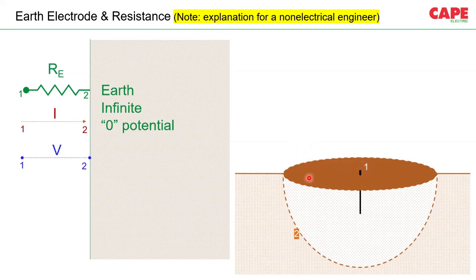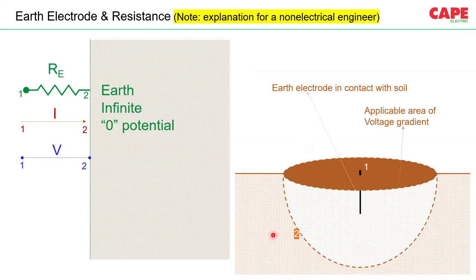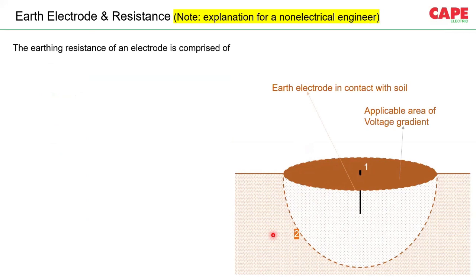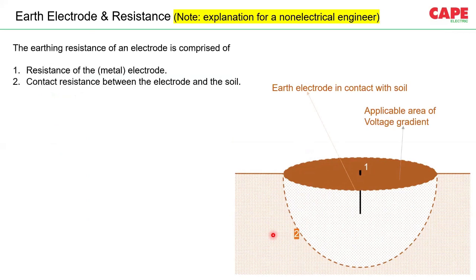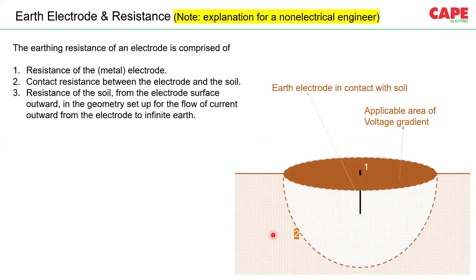Now, this resistance is over this particular area between point number 1 and 2. Earth electrode in contact with soil and the applicable area of the voltage gradient. I am trying to explain the earth electrode to you because it's a very influencing factor and it's a confusing factor. My idea is to explain the influence of this factor with the protective measure, automatic disconnection of supply.